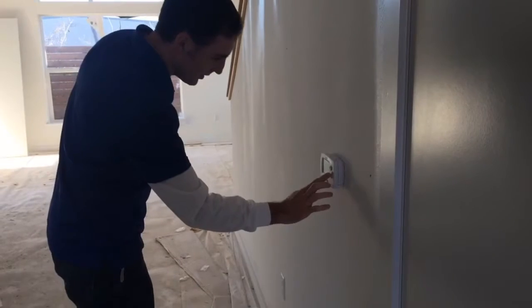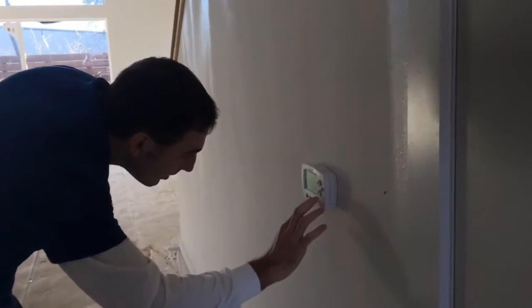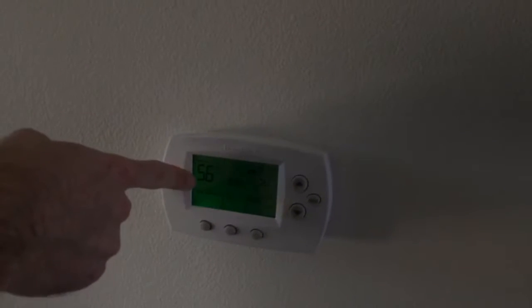Today we're going to be talking about airflow. So the first thing that we need to do when we're looking at airflows is turn the unit on. We typically measure airflows in max cooling. So we're going to turn the thermostat down as far as it's going to go and make sure that the fan speed is all the way up. So now we're set at cooling as far down as the thermostat will go. It's 56 in here, we're calling it 50.